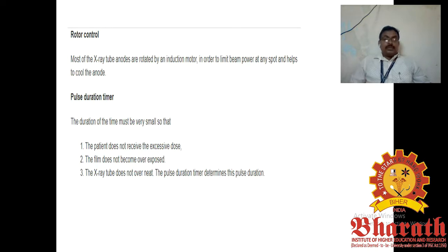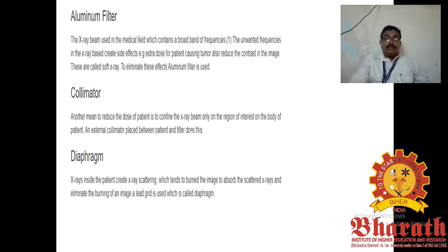Then the pulse duration timer ensures the patient does not receive an excessive dose, that is very important. X-rays may also be harmful. The film does not become overexposed, that is also a point to be taken care of. Then the X-ray tube does not overheat, right. So, that is also a problem. So, the pulse duration timer determines this pulse duration. So, each and every step is very critical in this process.